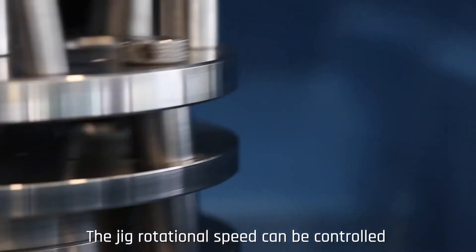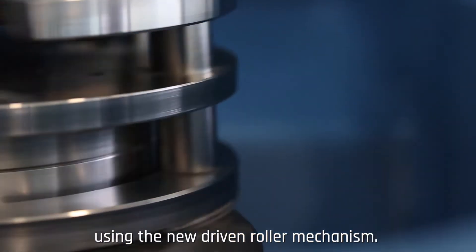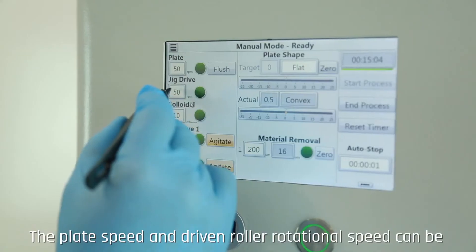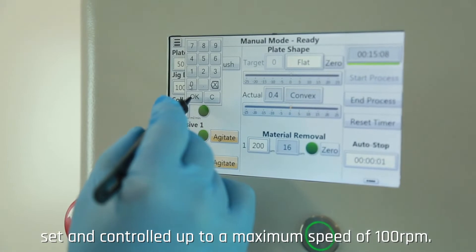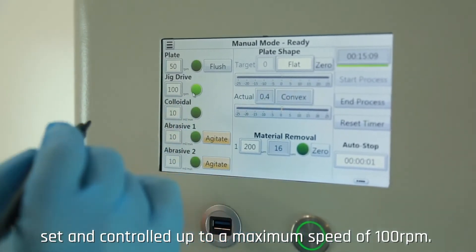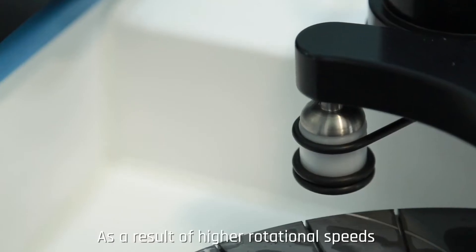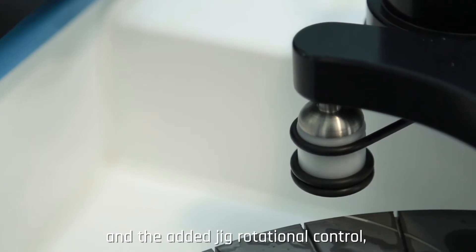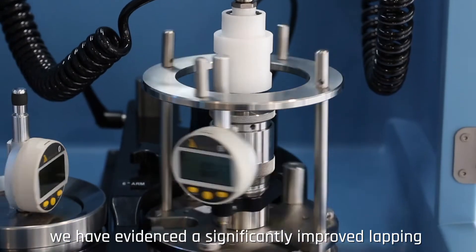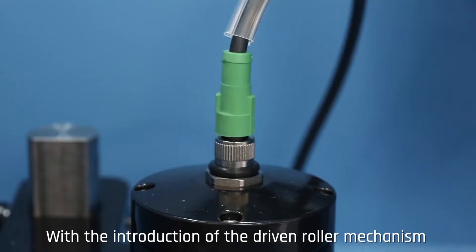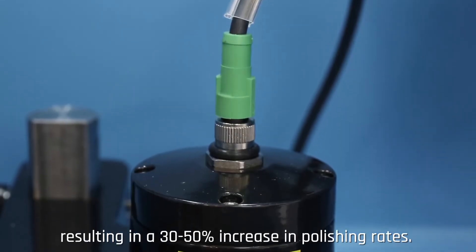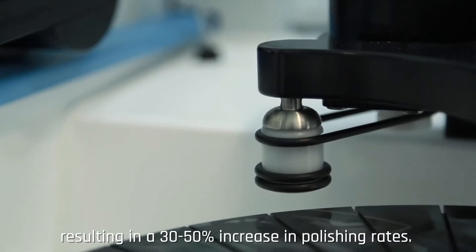The jig rotational speed can be controlled using the new driven roller mechanism. The plate speed and driven roller rotational speed can be set and controlled up to a maximum speed of 100 RPM. As a result of higher rotational speeds and the added jig rotational control we have evidenced a significantly improved lapping and polishing rate with the introduction of the driven roller mechanism resulting in a 30 to 50% increase in polishing rates.